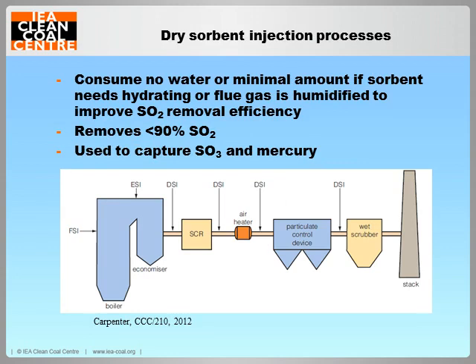Unlike the wet and semi-dry scrubber processes, the flue gas is not passed through a separate desulphurisation vessel. Sorbent is injected directly into the furnace, which is shown as FSI in this figure, or it can be injected into the inlet to the economiser, which is marked as ESI, or into the duct, which is marked as DSI. So consequently, there's a smaller footprint and the technology would be easier to retrofit.